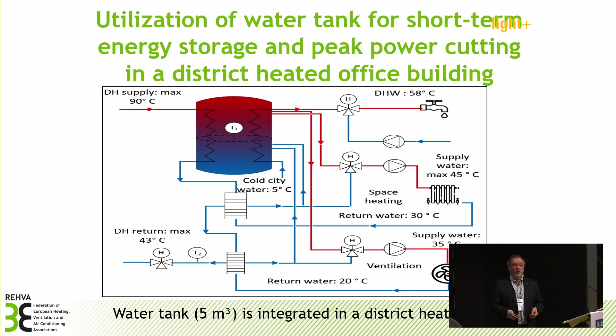One important thing to note is that when we integrate this kind of water tank in the system, we have to guarantee that the return water temperature is not higher than 43 degrees. That is the fixed requirement in district heating systems in the Nordic countries. It has to be guaranteed, and it's very important that we do not violate it, because then we are causing a big problem for the power plants. So we have two ways to cut the peaks: the building thermal mass, and a short-term energy storage in the building. In this case, the result is for a 5 cubic meter tank, which is still a reasonable size to implement in a real building based on space constraints.